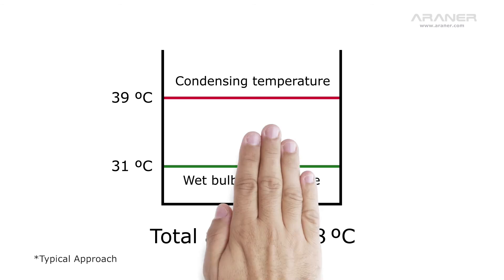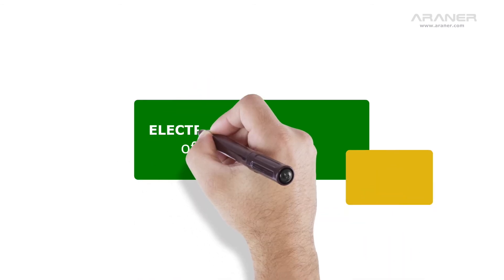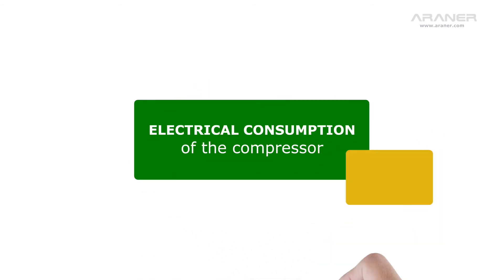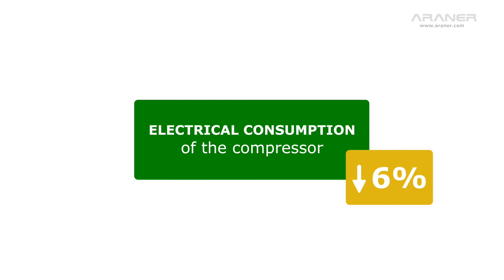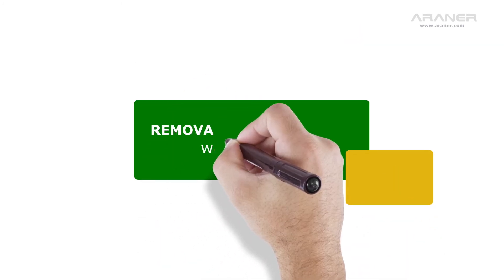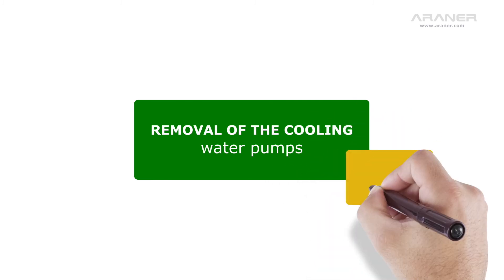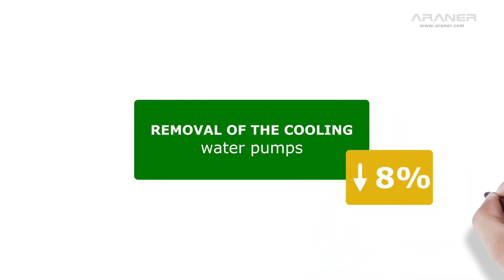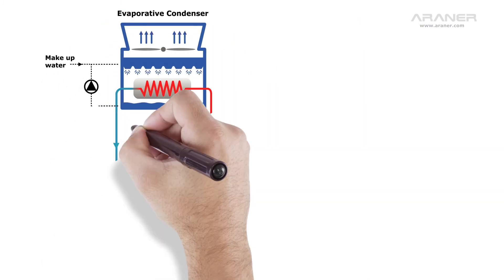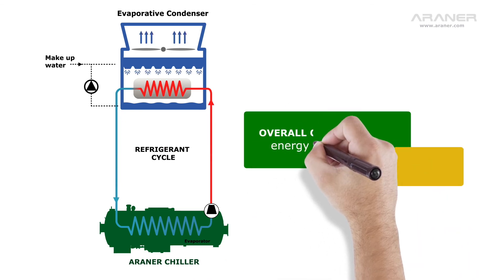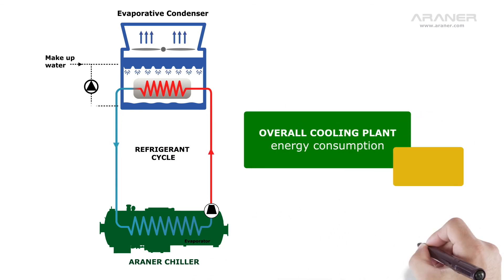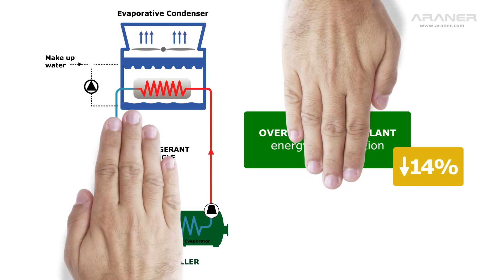By condensing at a lower temperature, we reduce the electrical consumption of the compressor by 6%, and an additional 8% from the deletion of the cooling water pumps, allowing us to decrease by 14% the overall cooling plant energy consumption.